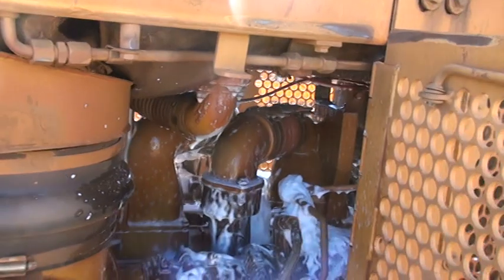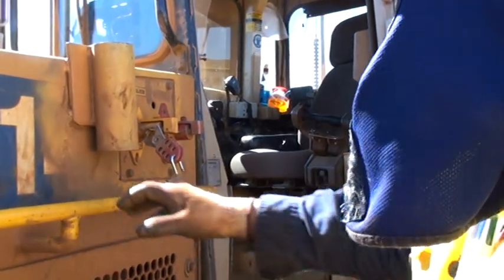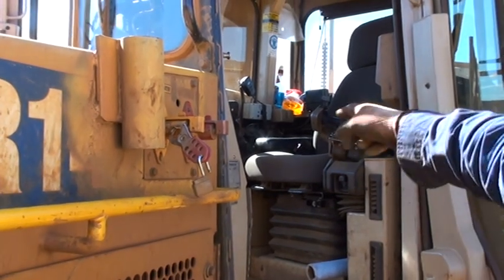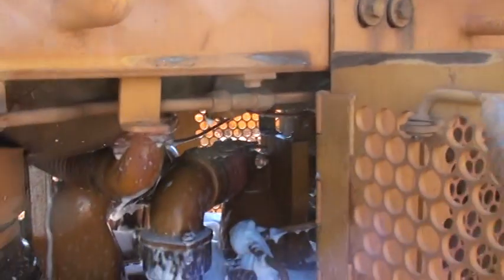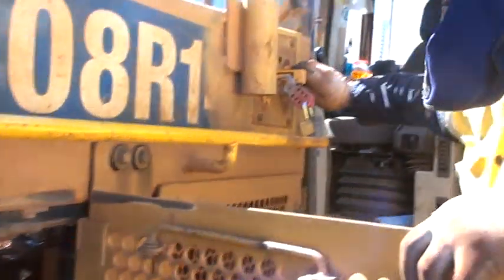The system installed on this machine is a loss of pressure system. That alarm will activate once the actuator has been initiated by a manual inside the cabin, or by burning the auto detection tube inside the engine bay. That alarm will only switch off once the machine has been isolated.